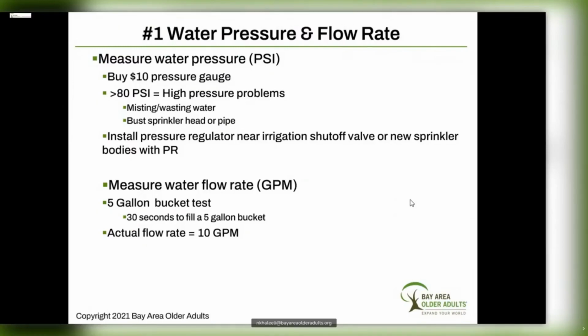Now, the flow rate can be measured by seeing how long it takes to fill a 5-gallon bucket of water. If it takes 30 seconds to fill a 5-gallon bucket, then the flow rate is 10 gallons per minute, or GPM. It is important to know the flow rate because it limits the number of sprinkler heads that can be placed in any one zone. You can also use a flow gauge to measure flow rate.